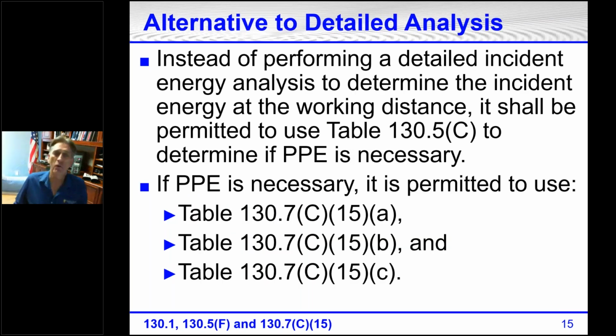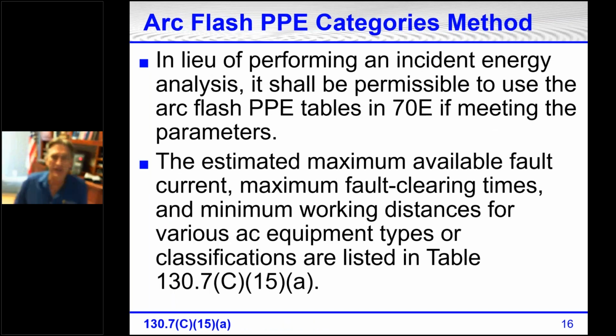Alternative, instead of performing a detailed incident energy analysis to determine the incident energy at the working distance, it's permitted to use table 130.5C to determine if PPE is necessary. And if so, then we're going to go to these other tables. Let's go ahead and look at them. Instead of performing incident energy analysis, it is permissible to use the tables in 70E if meeting the parameters.